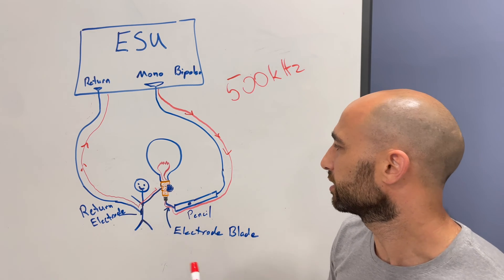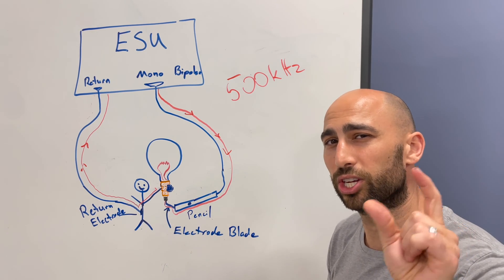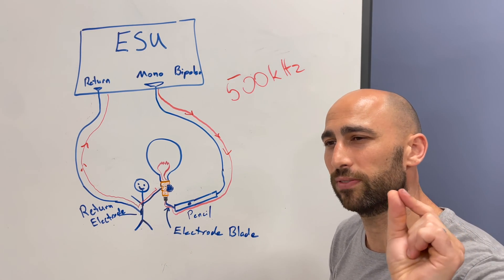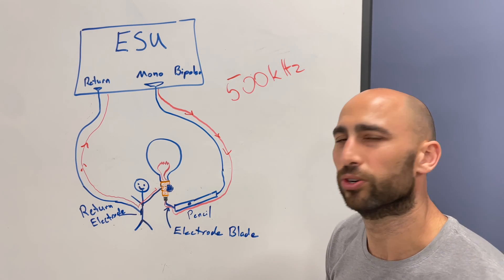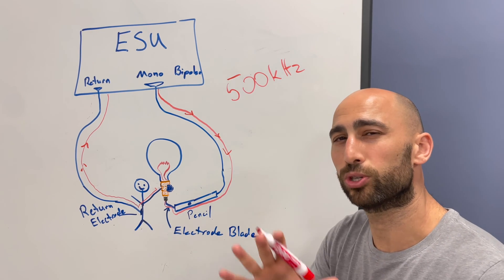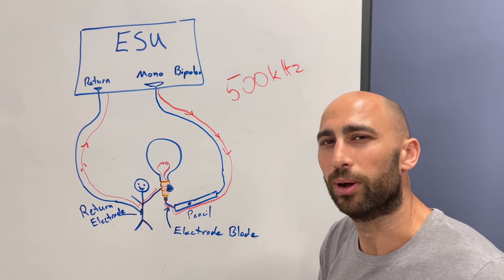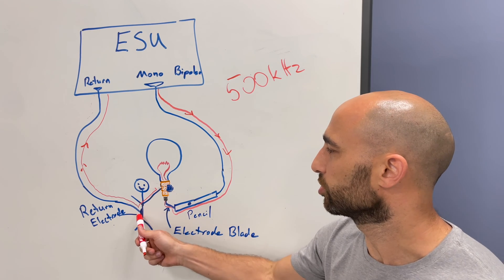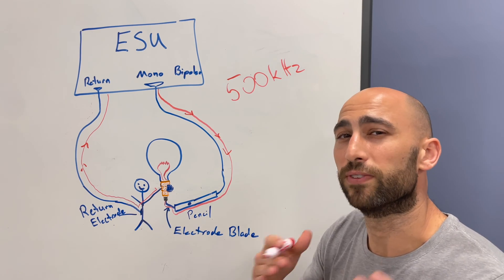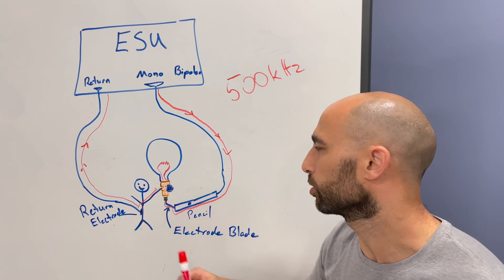The electrode is able to concentrate the current in a very specific area, whereas the return electrode is dispersing that current throughout the body. So if it's used properly, there's not any danger of getting burns.